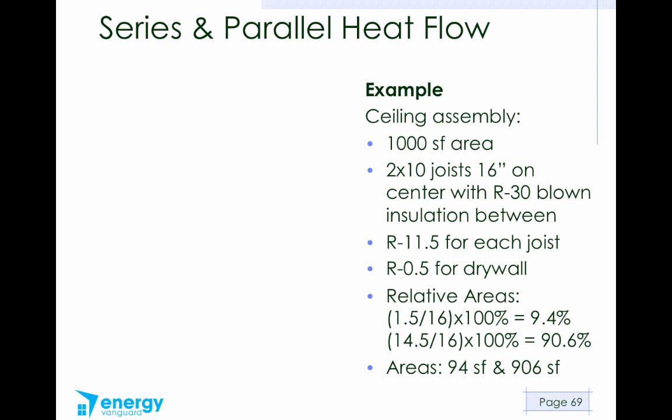If we multiply those percentages out, 9.4% of 1,000 square feet is 94 square feet, and 90.6% of 1,000 square feet is 906 square feet. Those are the areas of the ceiling joists and the insulation, respectively. If you want to give this a stab, see if you can try to find the average U value and the average R value now. Hit the pause button and see if you can get those calculations.